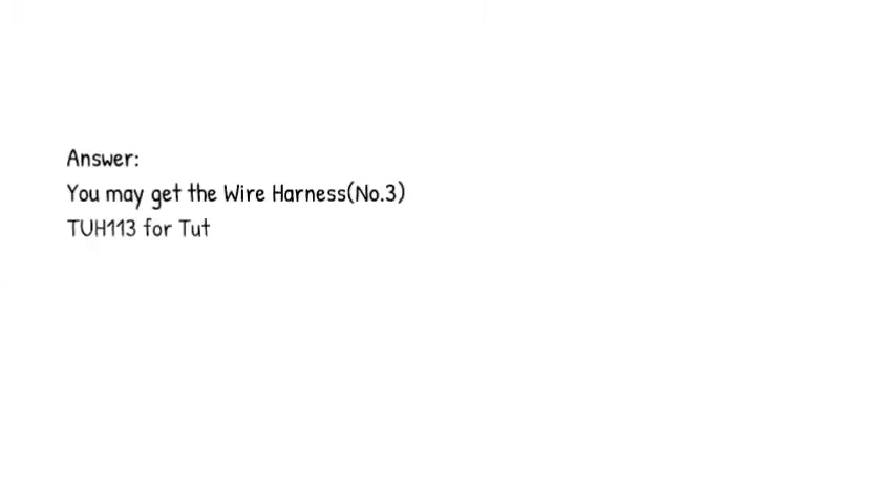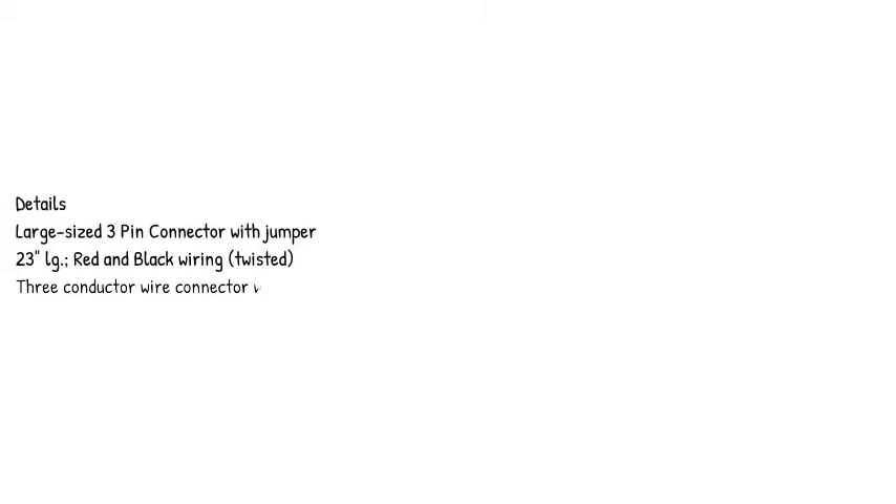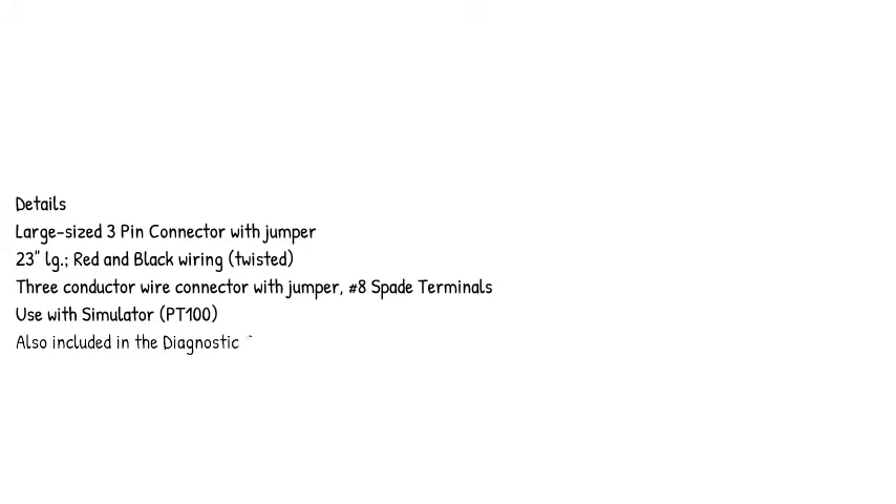Answer: you may get the wire harness number 3, TUH113 for the Tuttnauer sterilizer model in the link below. Large size 3-pin connector with jumper, 23 inches, red and black wiring, twisted, 3-conductor wire connector with jumper, number 8 spade terminals, used with simulator PT100. RPI part hashtag TUT114, also included in the diagnostic smart kit, RPI part hashtag TUC108.